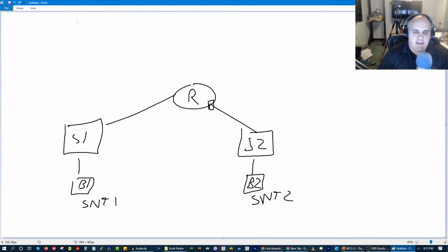And that's with BACnet. And I would say to you, yeah, you're absolutely right with BACnet, but IP traffic in and of itself, broadcasts are not going to travel. And the reason why is, imagine I initiate a broadcast on subnet 1, and it's able to be forwarded to subnet 2, subnet 3, subnet 4. It crosses these subnet boundaries. Before you know it, everyone in the world who's on the internet is sending broadcast messages all over the world and totally overwhelming networks. That's why we have broadcast boundaries, and we cannot send broadcasts outside of our subnet.